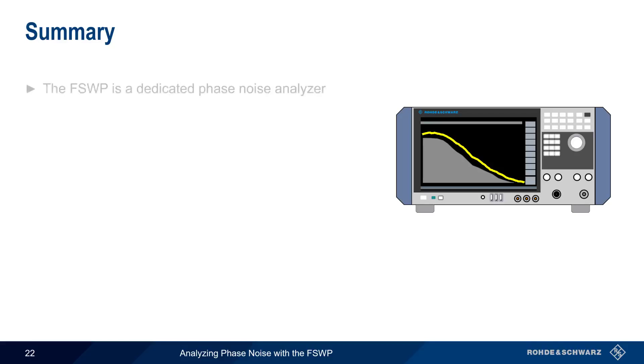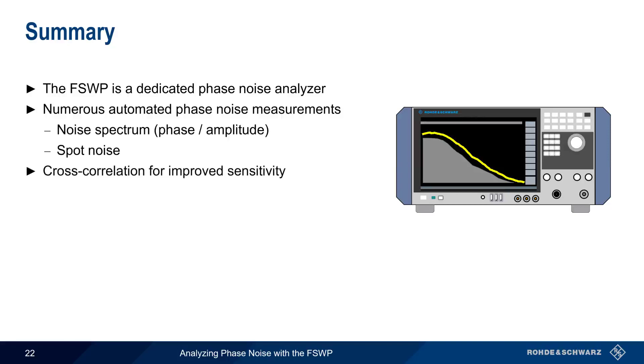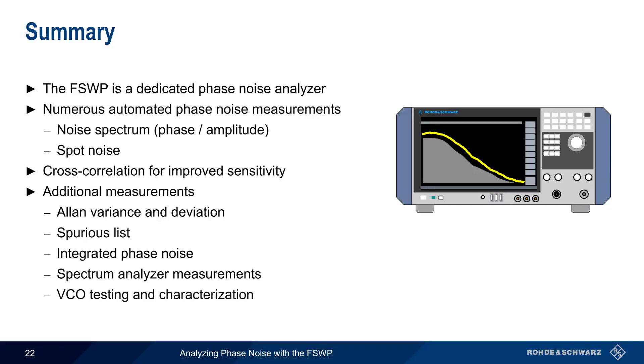Let's end with a brief summary. The Rohde & Schwarz FSWP is a dedicated phase noise analyzer that supports numerous phase noise measurement types. Results are most often displayed as a single sideband plot of noise spectrum and/or as spot noise at specified offsets. By adding a second internal measurement path, the FSWP can use cross-correlation to remove the influence of instrument noise and greatly increase measurement sensitivity. Additional measurements include Allan Variance and Deviation, spurious signal measurements, and integrated phase noise measurements. The FSWP can also perform standard spectrum analyzer measurements such as spur search and noise figure, and has integrated high-quality power supplies for testing voltage controlled oscillators. This concludes our presentation, 'Analyzing Phase Noise with Rohde & Schwarz FSWP.' For more information, please see the links in the video description.